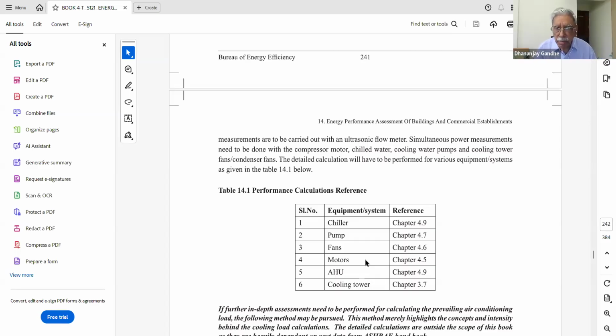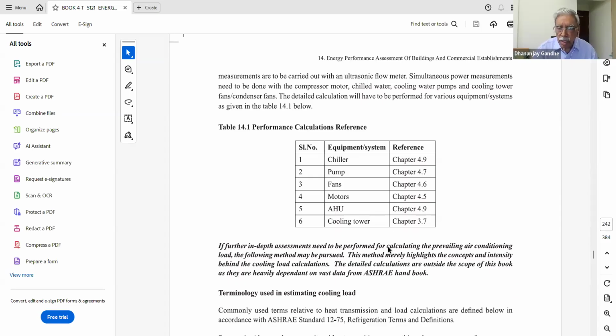Okay, so existing kilowatt of the chiller, divided by tons of refrigeration, which is the air conditioning load, that is worked out. Pump capacity is known. So for the air conditioning system, the kilowatt provided per ton of refrigeration, these figures are worked out. And the methodology for calculation of this is mentioned in chapter 4 for chillers, pumps, fans, and AHU, and also the cooling tower. So in chapter 3.7, those calculations are done on the existing figures of the HVAC system, the system that is installed.